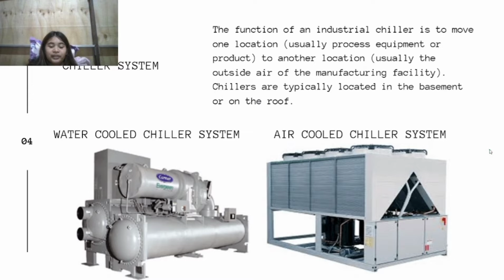Chiller system. The function of an industrial chiller is to move heat from one location, usually process equipment or product, to another location, usually the outside air of the manufacturing facility. Chillers are typically located at the basement or on the roof. Rooftop chillers tend to be air-cooled, whereas basement chillers tend to be water-cooled. It is used to cool products and machinery, and knowing that a wine warehouse stores wine and this wine needs to be preserved, this chiller system is very important in a warehouse.